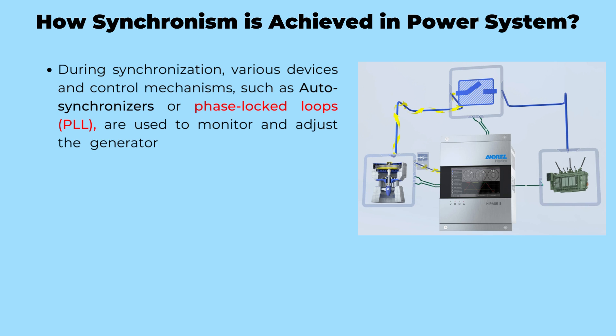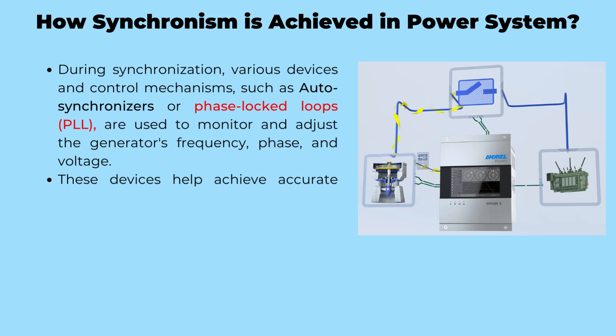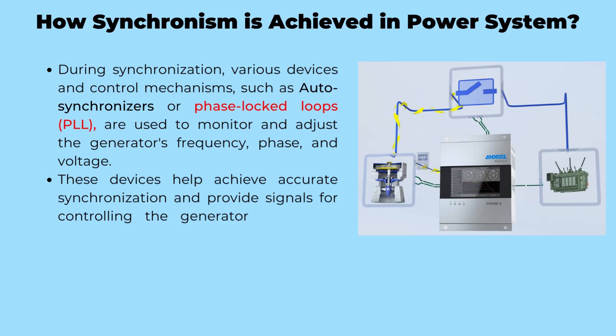Autosynchronizers are devices designed to monitor and adjust the frequency, phase, and voltage of the generator being synchronized. They compare these parameters to the corresponding values in the power system and provide feedback signals for controlling the generator's excitation system and prime mover. Phase-locked loops, or PLLs, are another commonly used control mechanism for achieving synchronization in inverter-based resources. These devices ensure that the generator's frequency, phase, and voltage are in harmony with the power system, allowing for a smooth and seamless connection.